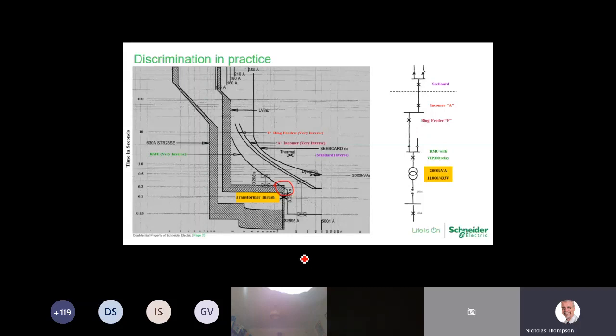It may be acceptable. It is the first LV device, and there is intertripping in this one, so it may be that it's acceptable. It may be deemed unacceptable, and then the juggling would need to be taken into account, changing the curve parameters on the VIP 300, which doesn't have really fine settings. You can't do fine settings with it like you can with a MiCOM or a SEPAM or an ABB relay, for instance. But this is one of the things you would need to consider.